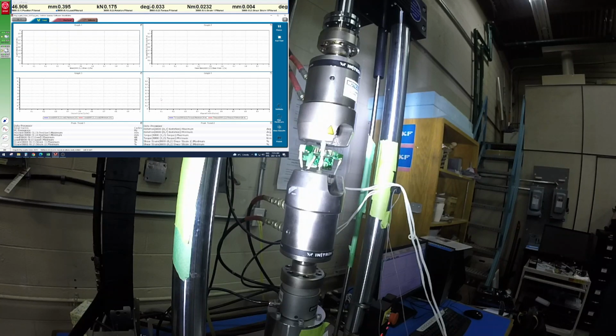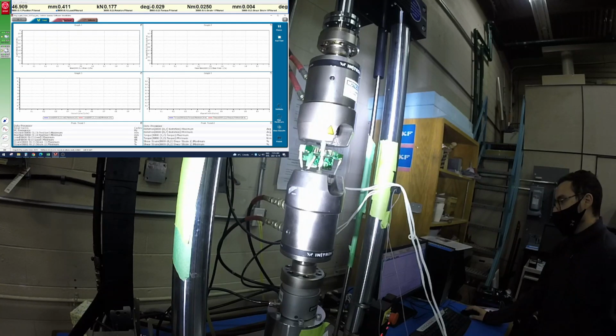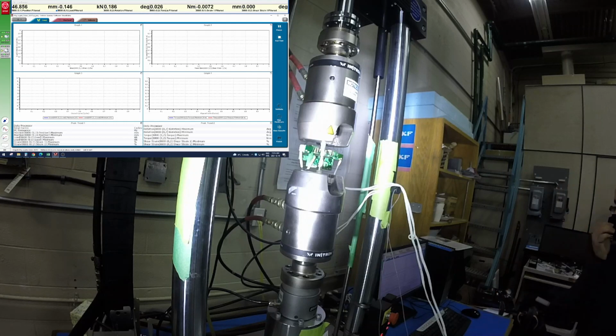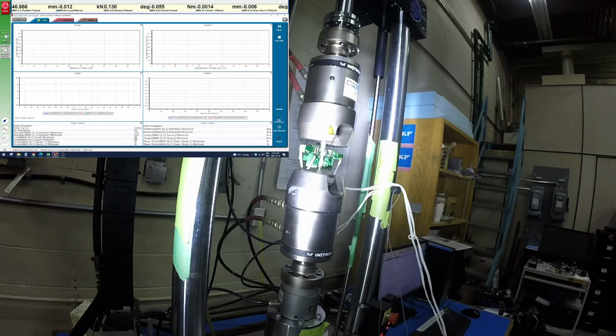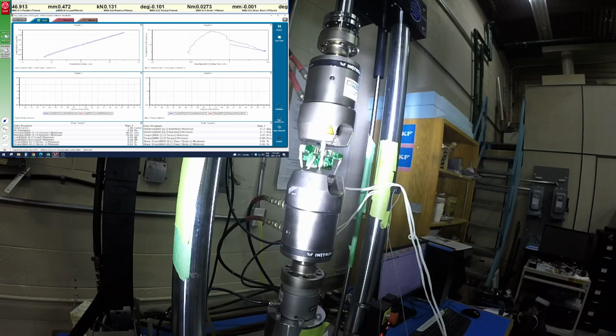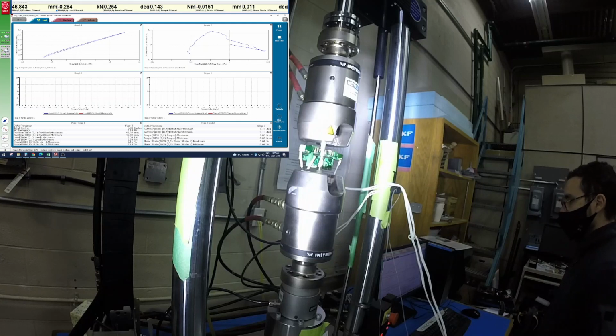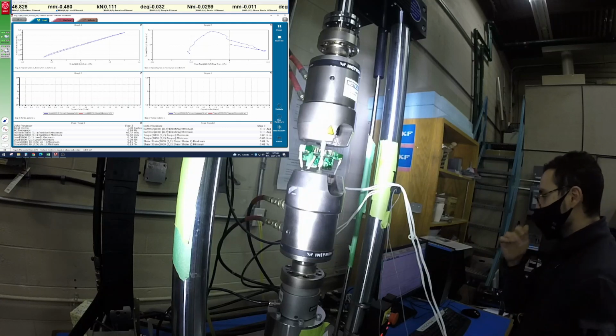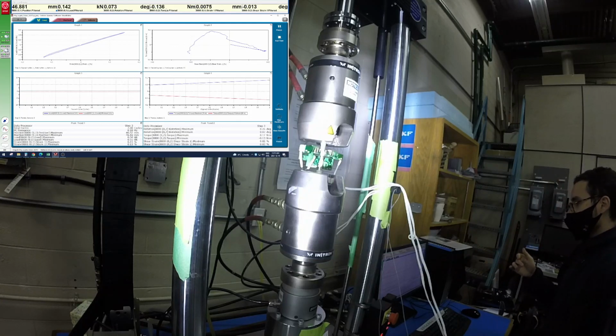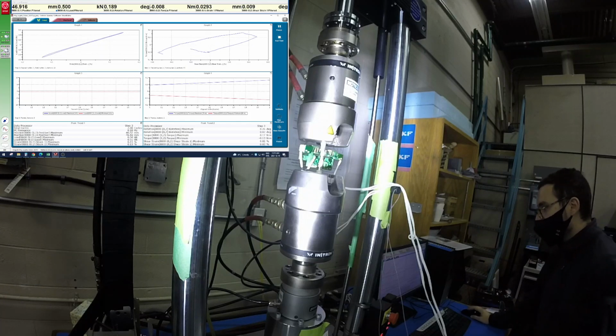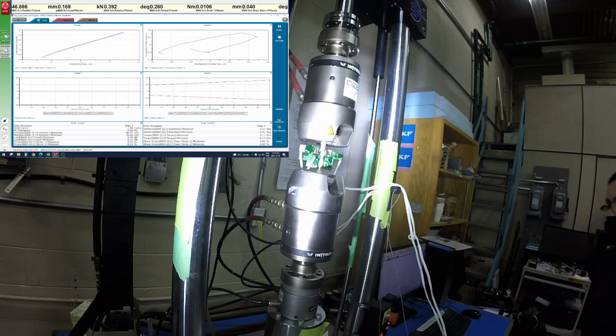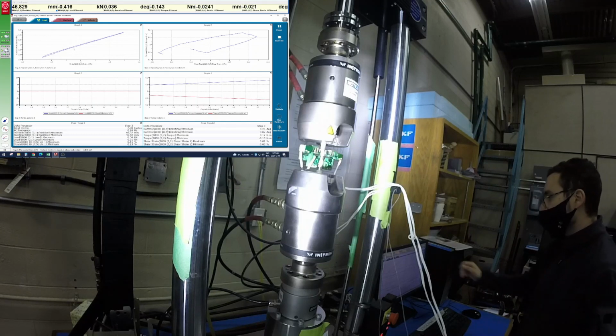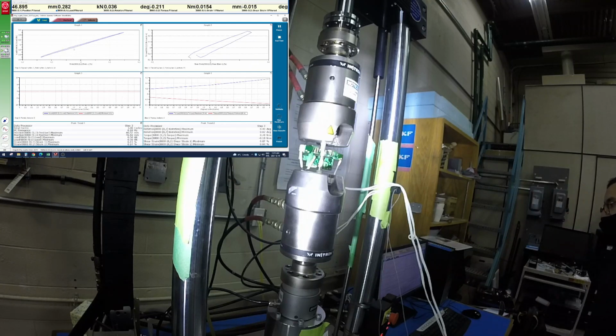And you'll see now the forces and the torques are changing. Since the test frequency is so slow and the amplitudes are quite low, you won't see a lot of updates on the screen. You're going to see an update every 10 seconds. So you should be able to see on the left an axial stress strain hysteresis loop, and on the right you'll see a shear stress strain hysteresis loop.